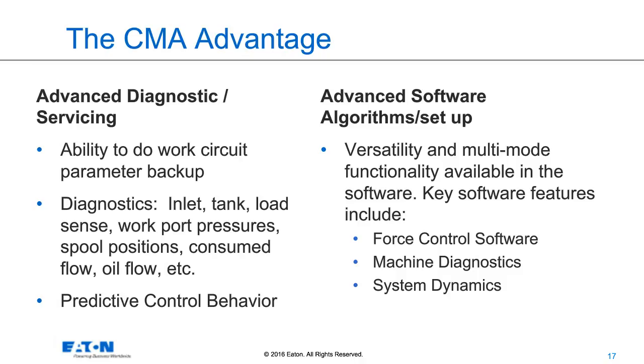Along with having all those sensors, we have diagnostic capabilities - anything from inlet, spool position, to consumed flow and oil flow. Those are all options available to be monitored and reported out to customers through this valve. Finally, we believe you have the capability to do some predictive control behavior. If you can monitor pressure and flow of the valve, you're getting monitoring capability of other hydraulic components within the system.